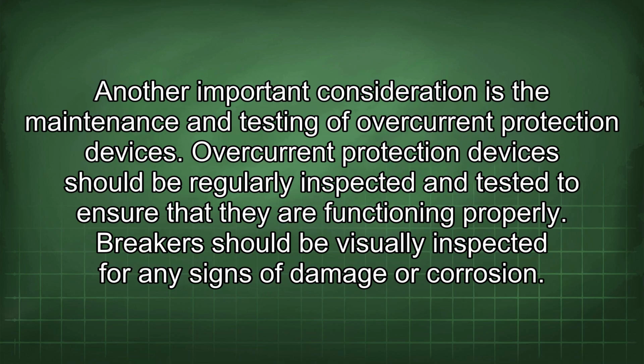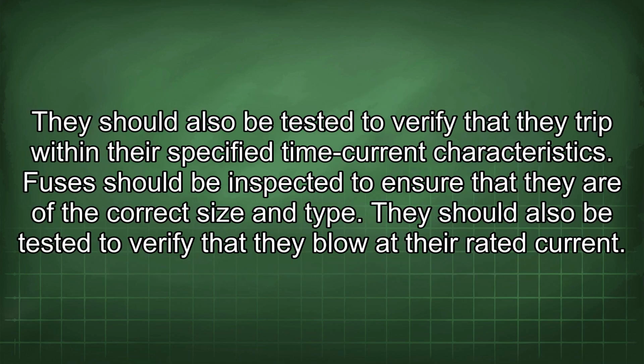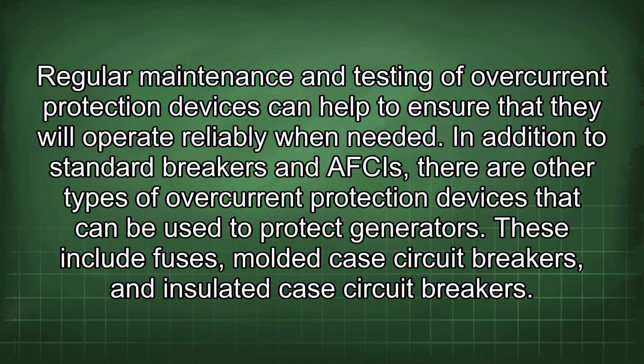Another important consideration is the maintenance and testing of overcurrent protection devices. Overcurrent protection devices should be regularly inspected and tested to ensure that they are functioning properly. Breakers should be visually inspected for any signs of damage or corrosion. They should also be tested to verify that they trip within the specified time current characteristics. Fuses should be inspected to ensure that they are of the correct size and type. They should also be tested to verify that they blow at their rated current. Regular maintenance and testing of overcurrent protection devices can help to ensure that they will operate reliably when needed.